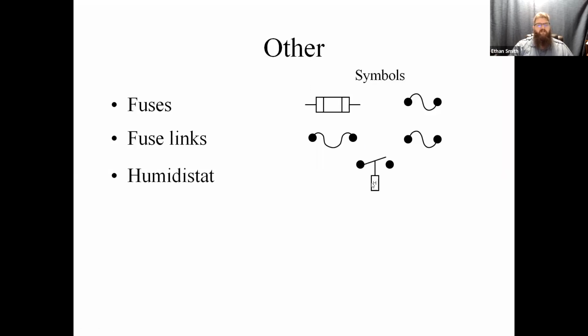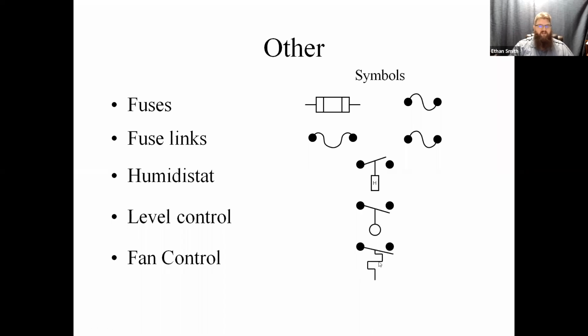Other types of switches you'll have, guys, are humidistats. So this would be a humidity sensing switch. Opens on a rise in humidity, closes on a drop in humidity. So this would be for a humidifier, not a dehumidifier. Float controls, we see these in high-end swamp coolers. We see them in hydronic systems, steam boilers, things like that. And this is basically just a float attached to a switch. Okay. Fan controls, these are just thermal switches. Anybody who's ever had a low boy or a furnace older than about 25 years, you'll see these auxiliary fan controls outside the furnace or inside the furnace sometimes. They're becoming rarer. But in the end, guys, they're all just switches. Okay. Any questions, guys, about any of the stuff we've covered?